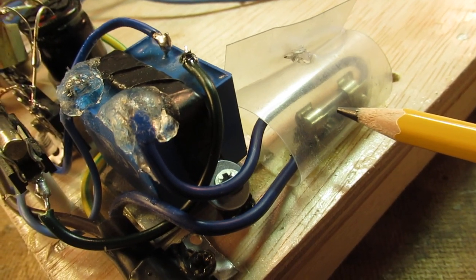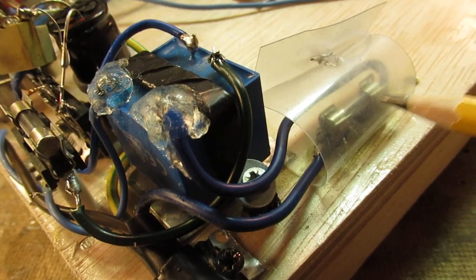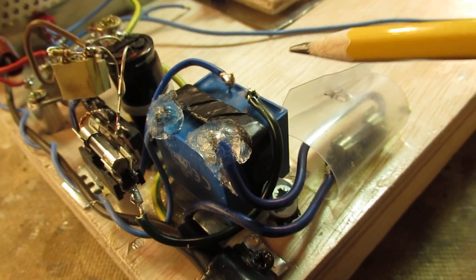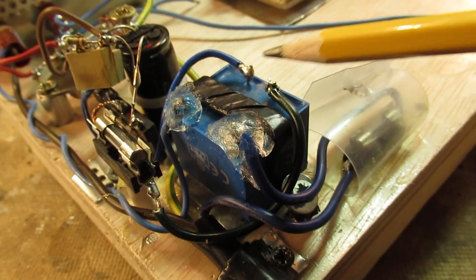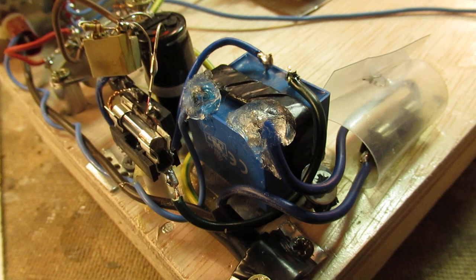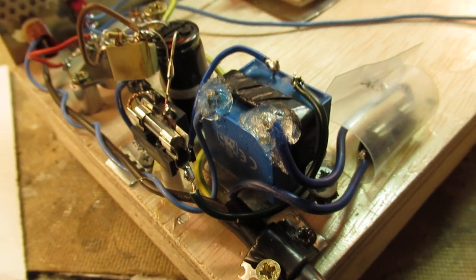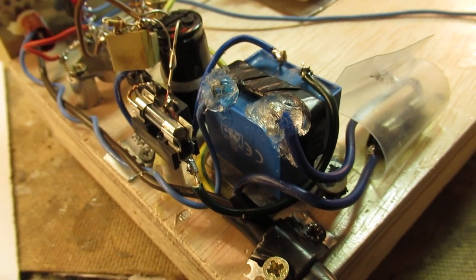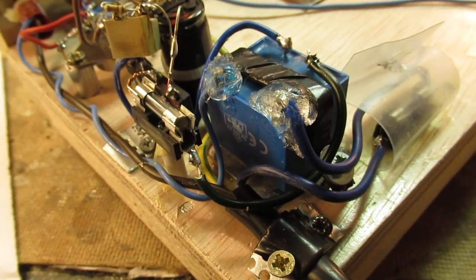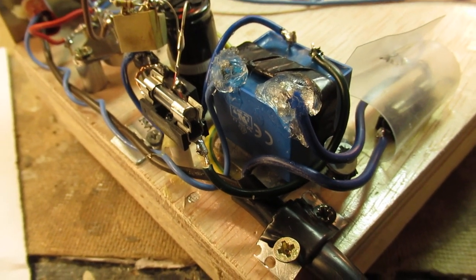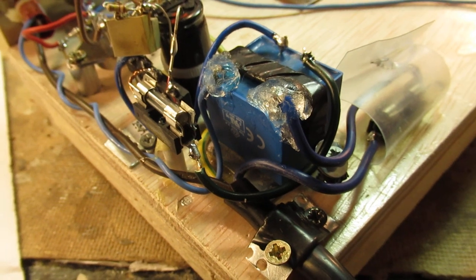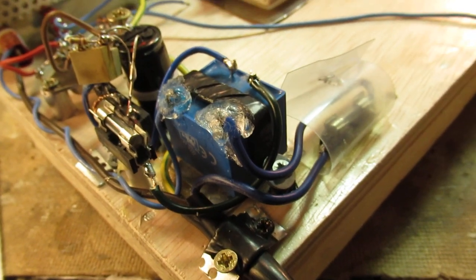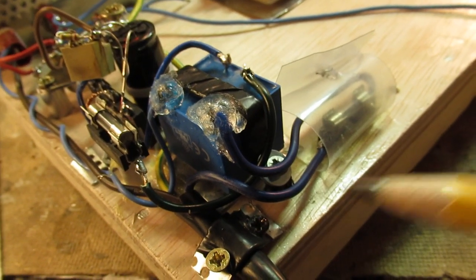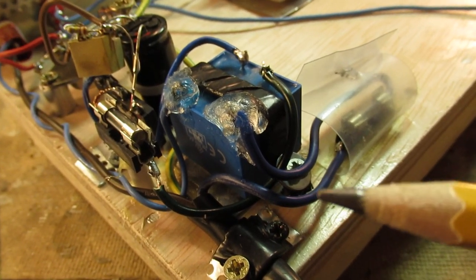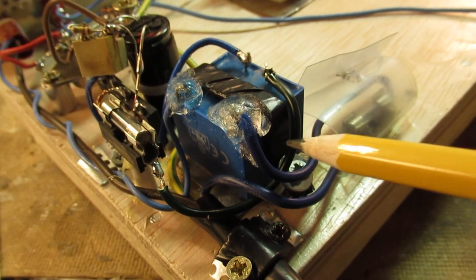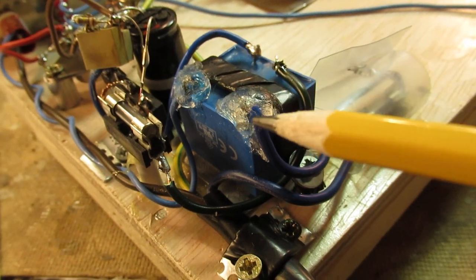You have to take account of the inrush current, because when such a transformer on its secondary is loaded with a resistor or whatever, and you switch on 230 volts AC at 50 hertz or 110 volts AC at 60 hertz, doesn't matter, there is an inrush current.